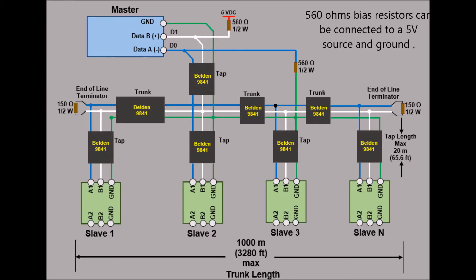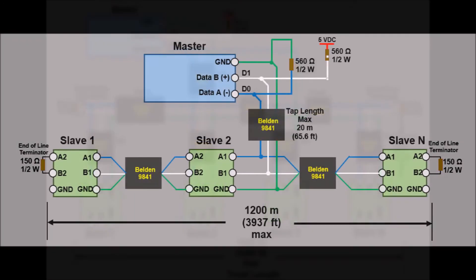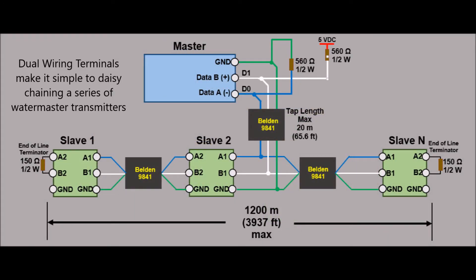A pair of 560-ohm resistors can be connected on the RS-485 balanced pair to bias the signals — a pull-up resistor to a 5-volt source on the D1 circuit and a pull-down resistor to the common circuit on the D0 circuit. The Watermaster has dual wiring terminals for RS-485 connections, which provide a means of connecting the in and out bus cables for daisy chaining directly onto the bus.